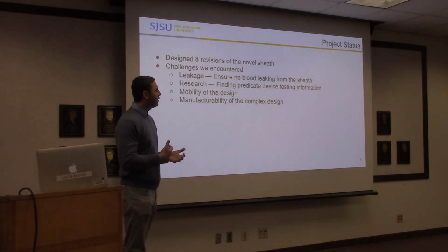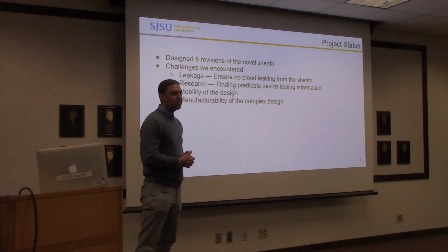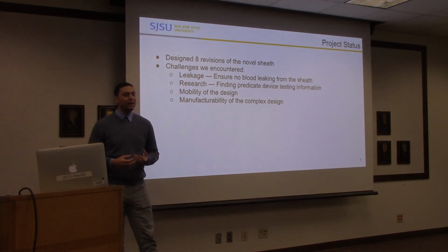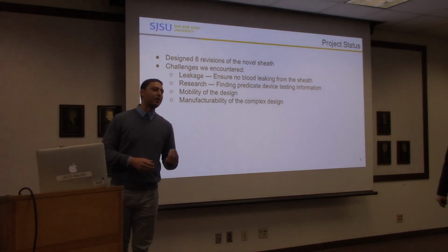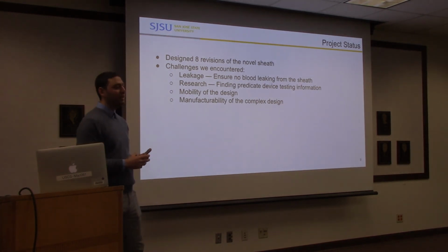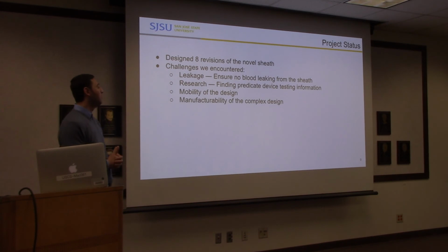Some of the challenges that we encountered is the leakage: making the sheath leak resistant so that it does not cause any leakage when it's inserted in the blood vessel. That was one of the main challenges that we spent most of the time on.